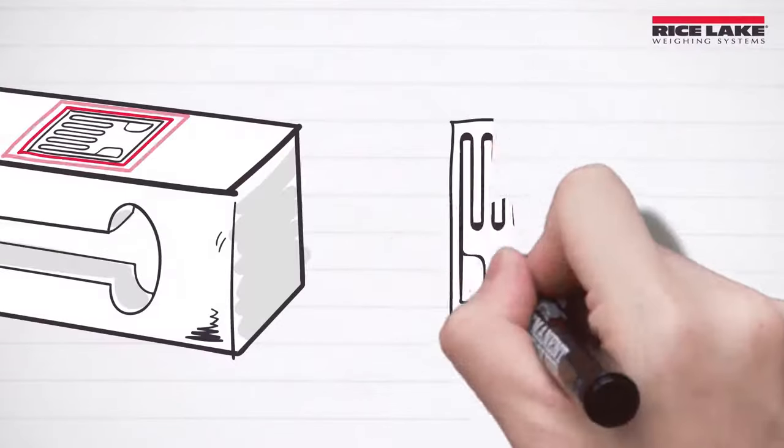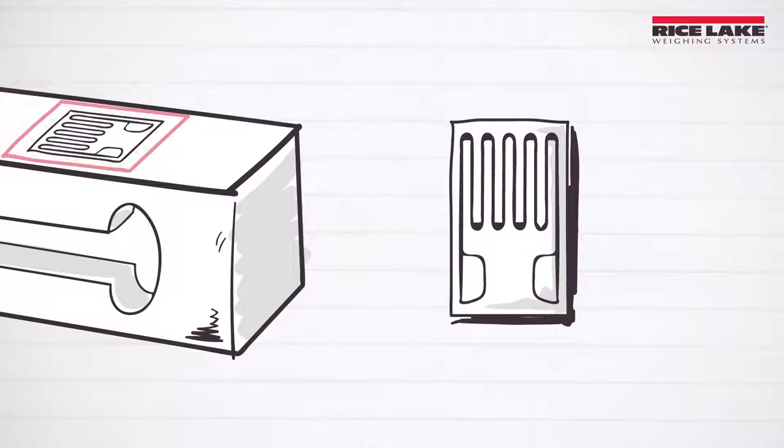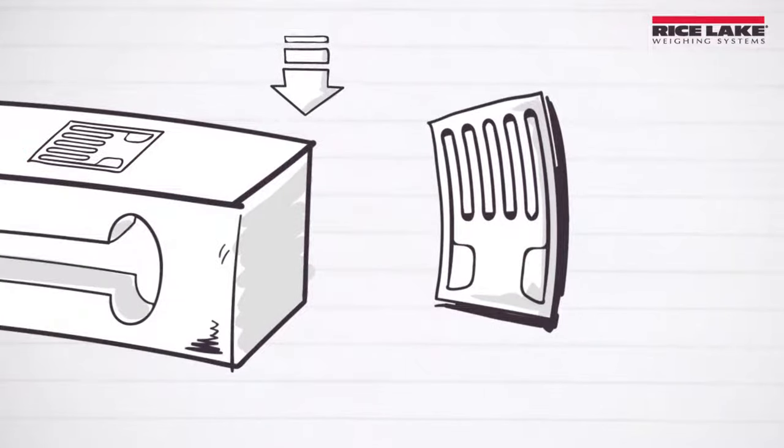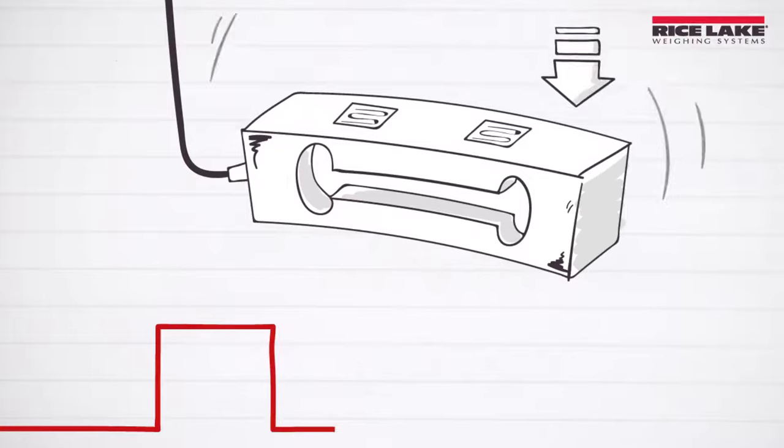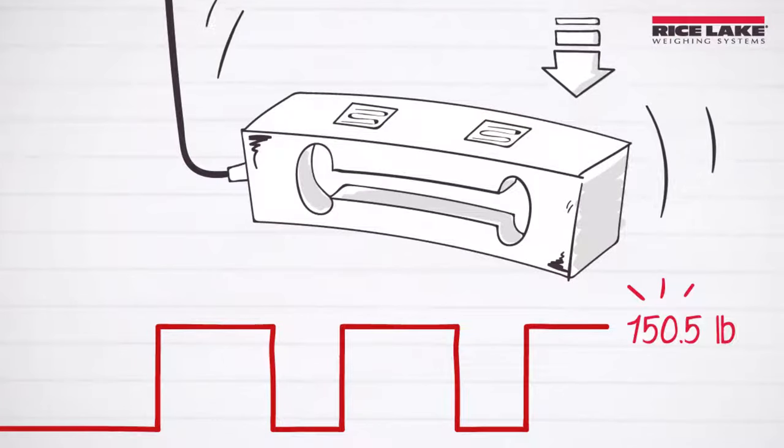This analog signal change is due to the amount of electrical resistance the bending causes to a small device inside the load cell called a strain gauge. The load cell's analog signal change is then read by an electronic device and turned into a digital weight value.